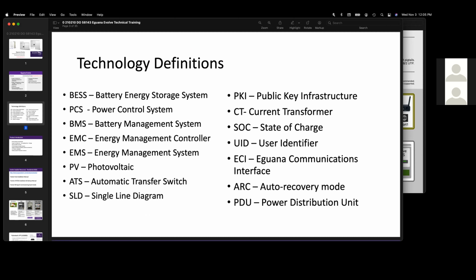Will's question is, what is the RSOC and DOD of the battery module? If you mean reserve SOC, that's user configurable. There are various low-end thresholds. The first threshold is the reserve as defined by the consumer, because it is consumer-owned equipment. They have a slider to control how far it discharges to the first stopping point. Below that, based on the total capacity of the system, there's a minimum reserve. Below that are critical reserve levels where maintenance charge would step in. And even further below that, if the maintenance charge, something was to fail, the battery BMSs have their own thresholds where they would go into hibernation.